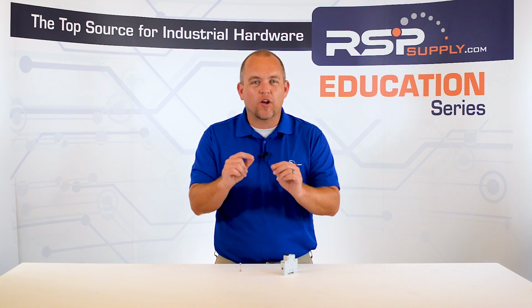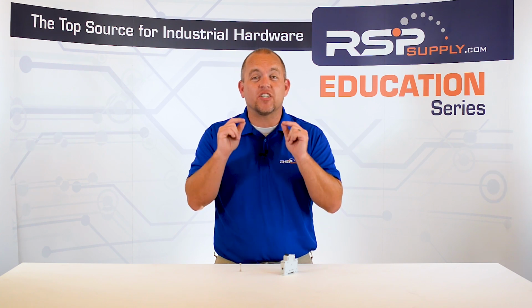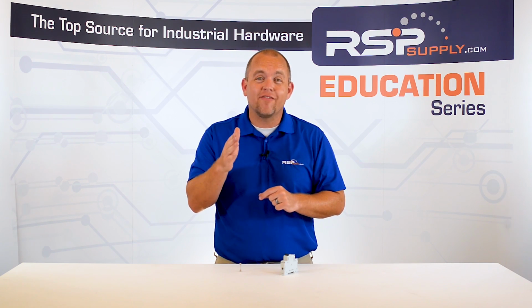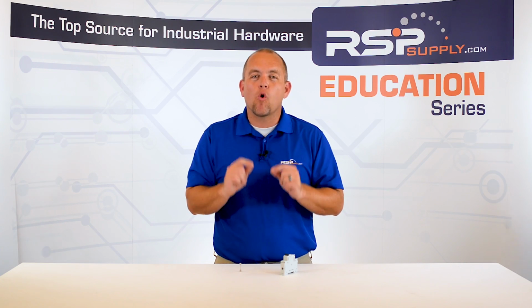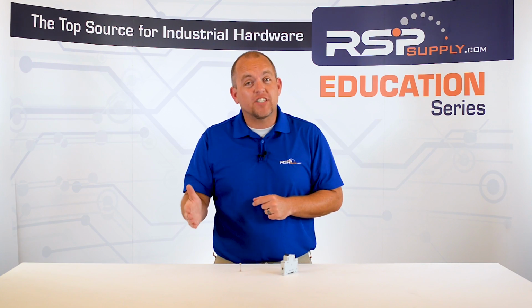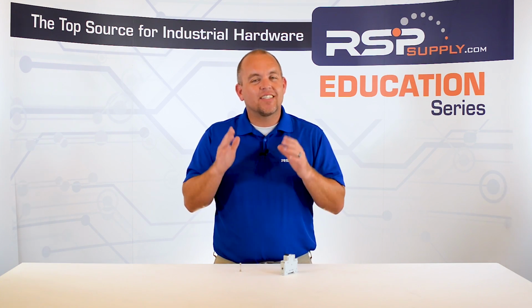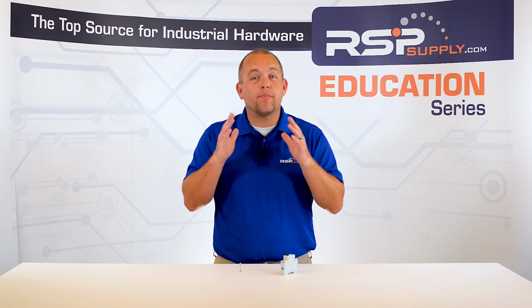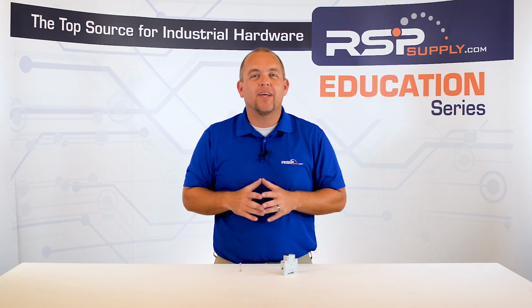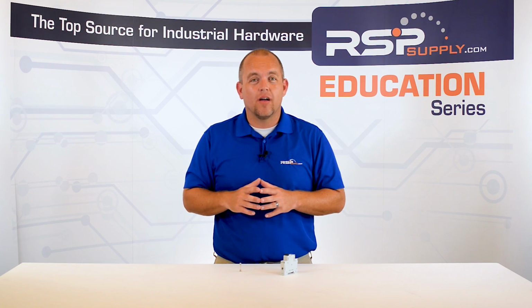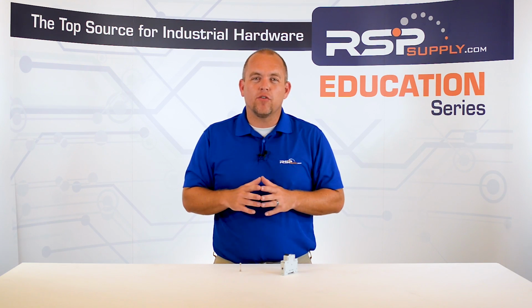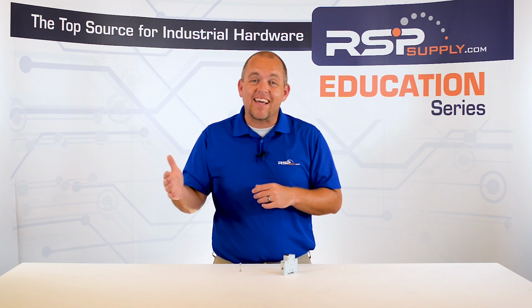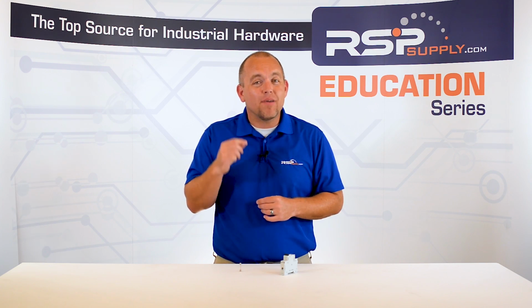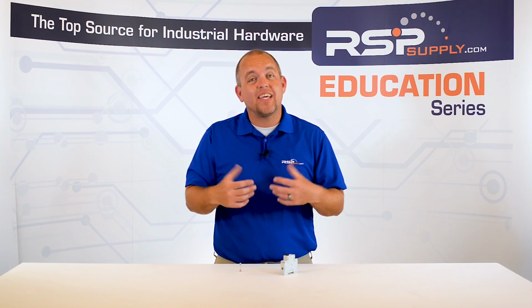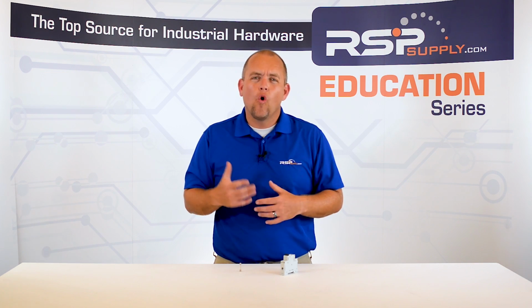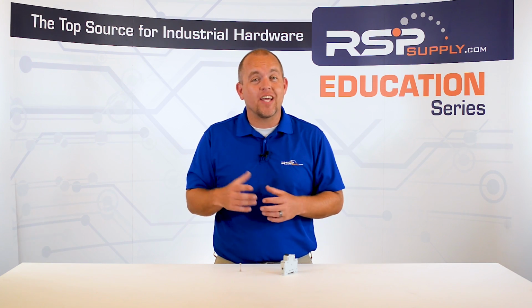So when it is critical to interrupt power in the event of a surge or overcurrent event very quickly, it is more common to see fuses being used in these scenarios. In some cases, fuses may even be required by code because of their quick interrupting nature. A downside of using fuses is the fact that they need to be replaced each time they are used. This can be very expensive, especially in higher current applications or where specialty fuses are needed.